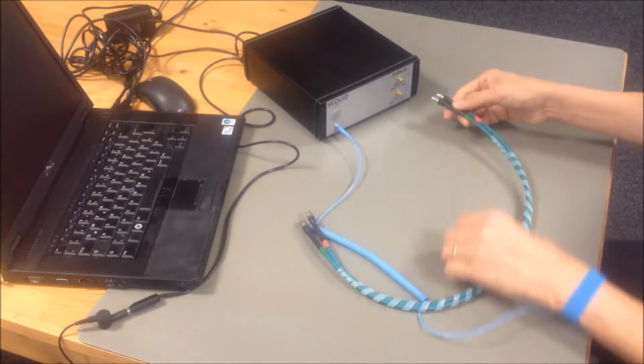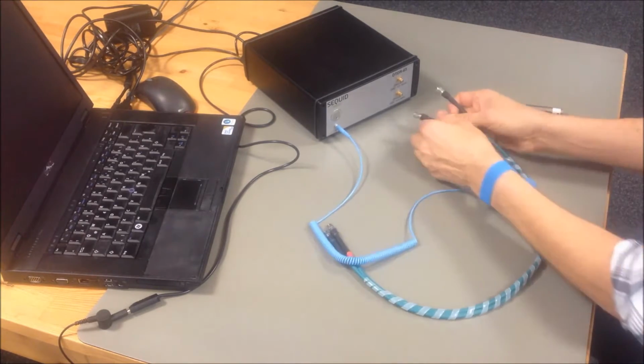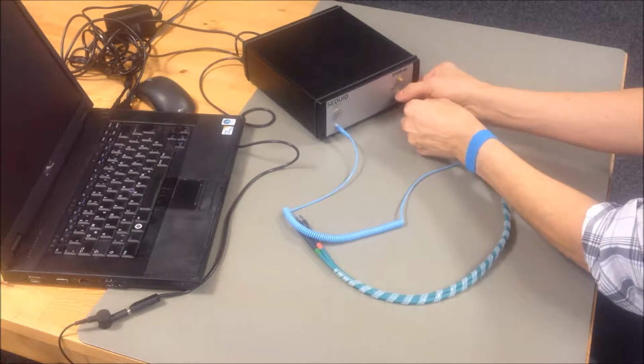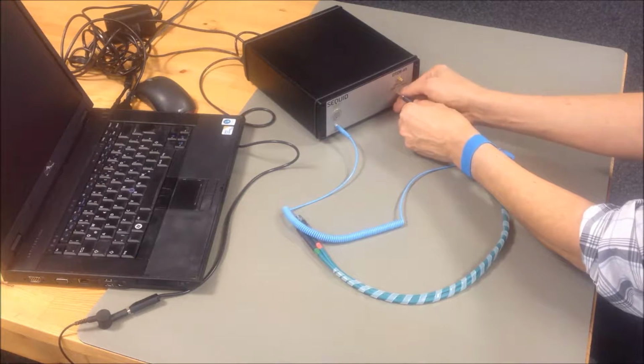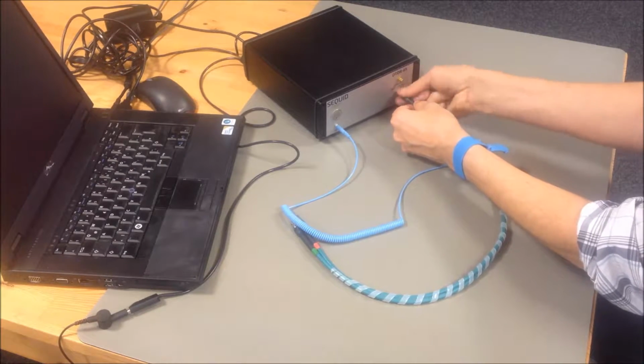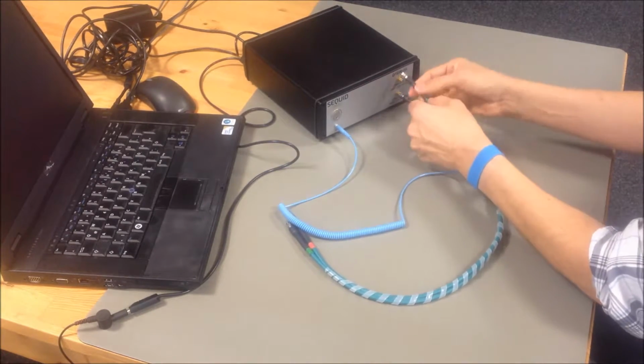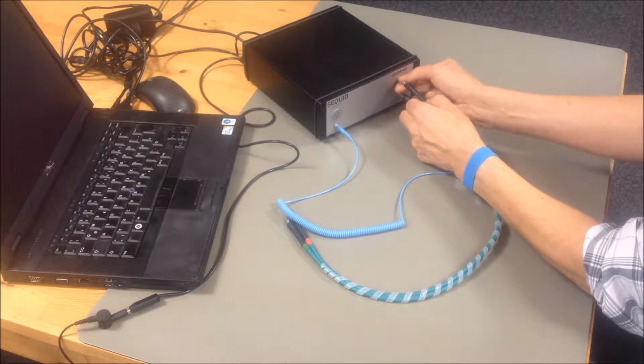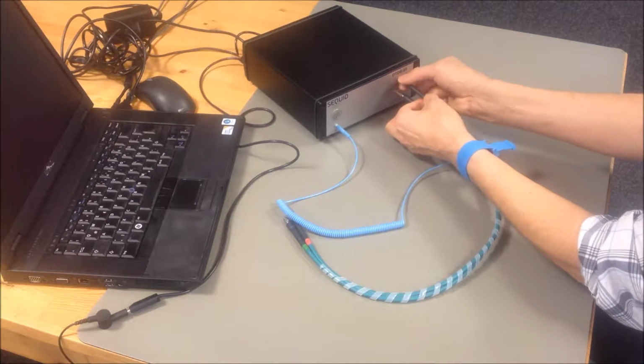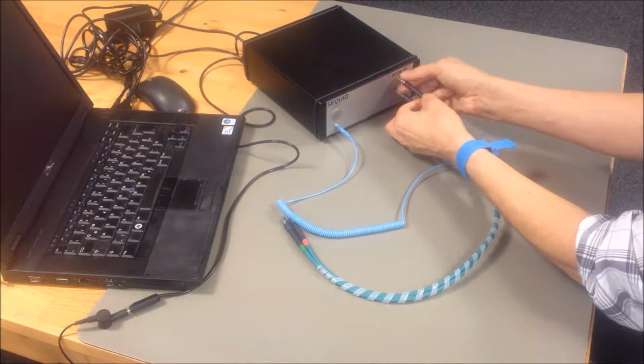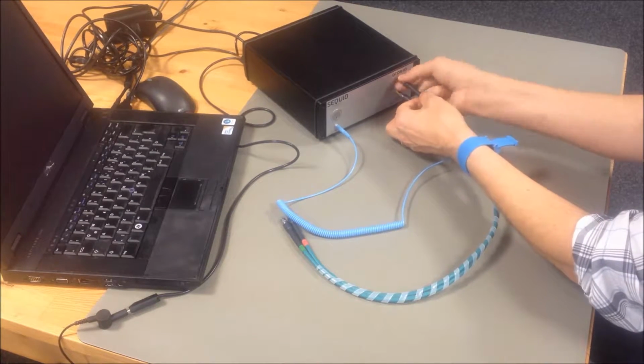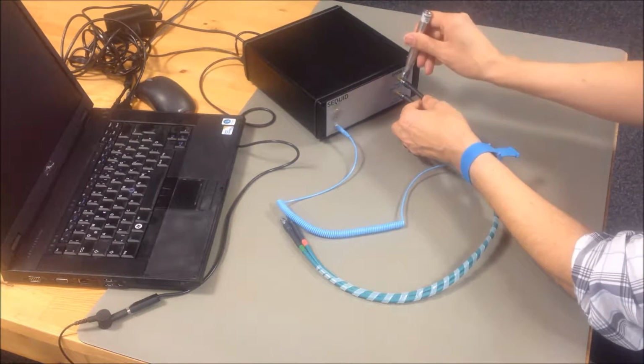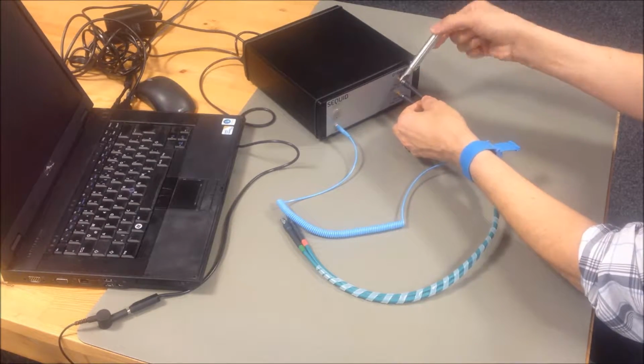We start connecting the phase-matched SMA cable to the instrument. So, please consider the markings. In this case, it's green and red. It can also be gray and black, for example. Fasten the SMA cables hand tight, and then you can lock them with a torque wrench afterwards.